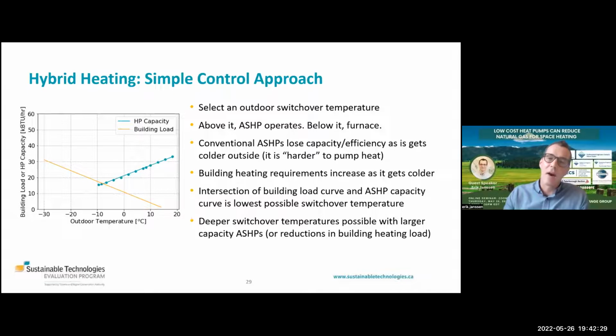At the same time, our building heating requirements are going to be increasing as it gets colder outside. And this should be pretty straightforward. At some point, the amount of heat that the heat pump can supply and the amount of heat that our home needs, those two curves are going to intersect. And that intersection is really the lowest possible switchover temperature that we could get for a home. Because below that temperature, the heat pump is below the building load and doesn't have enough heating capacity.